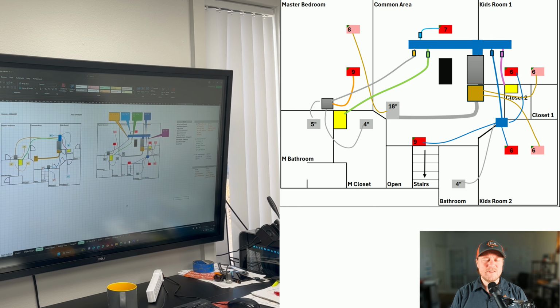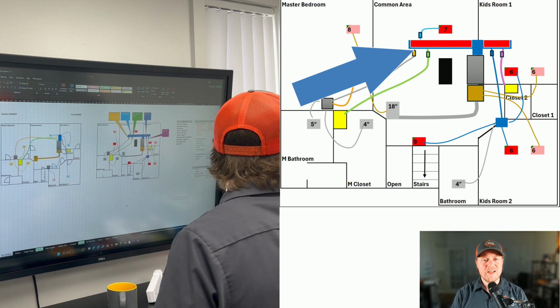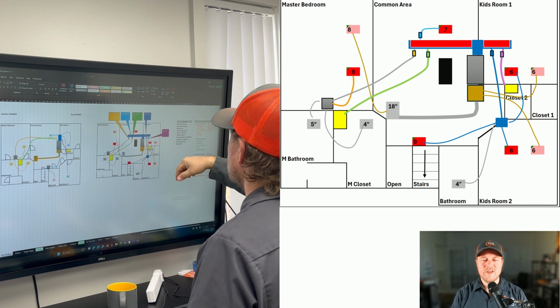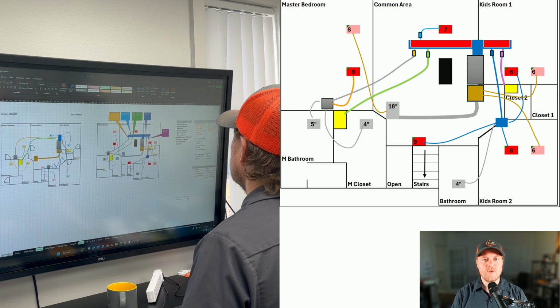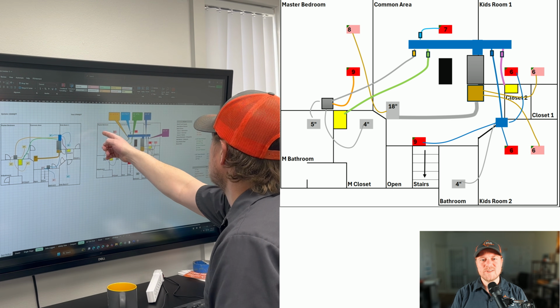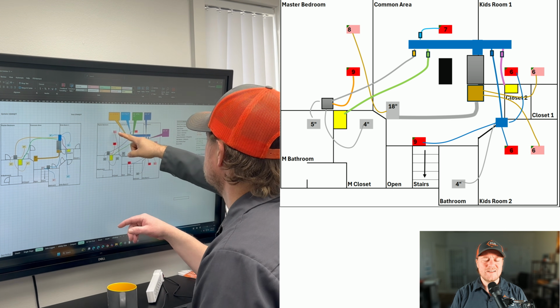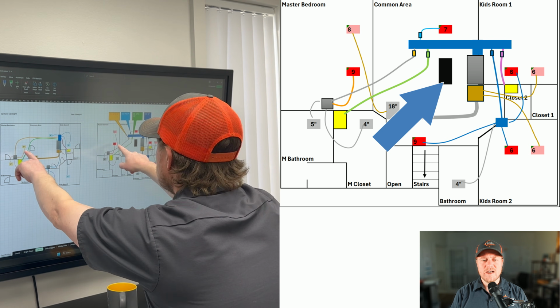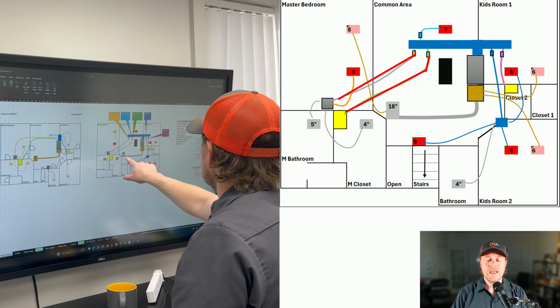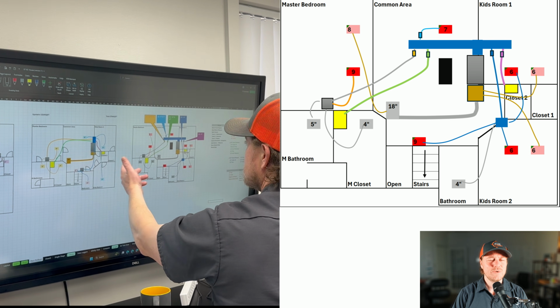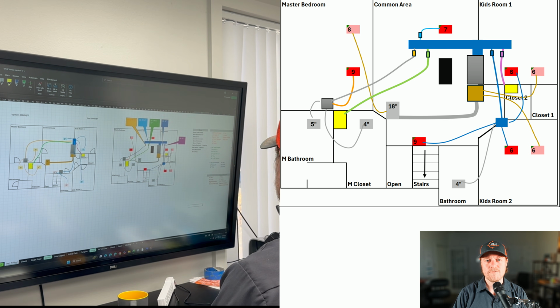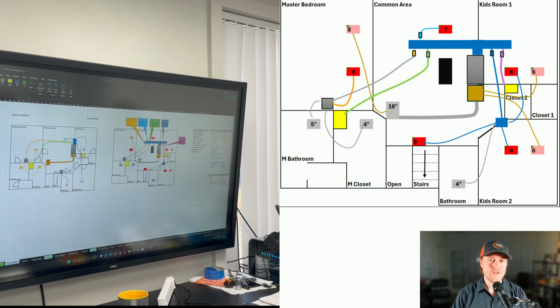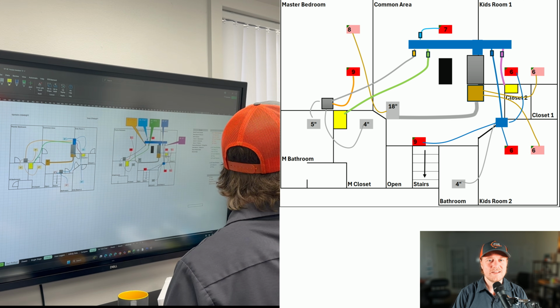My idea to solve this is to build out a large trunk that attaches to each side of the supply plenum. One side's going to be 8 foot long and the other side's going to be 4 foot. And the reason why I have to make one side longer than the other is because the attic access is right here, and I need the ducts coming off of them on the other side of it. Any other design that I'm coming up with is simply going to require us to remove a lot of framing, and I'm not wanting to do that. That being said, this is the best design that I'm coming up with.